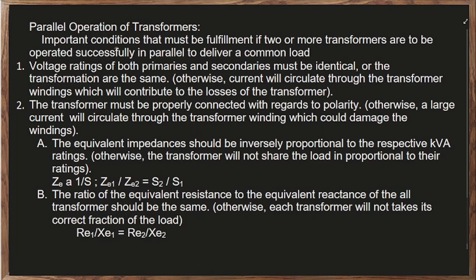Okay, parallel operation of transformers. Important conditions must be fulfilled if two or more transformers are to be connected in parallel. First, the voltage ratings of both the primary and secondary must be identical, so their primary and secondary voltages must be the same. Otherwise, current will circulate through the transformer windings, which contributes to the losses of the transformer. When they are not the same, one becomes a load on the other transformer, so the efficiency will be lower, no?